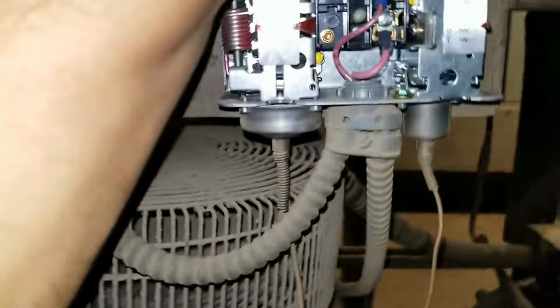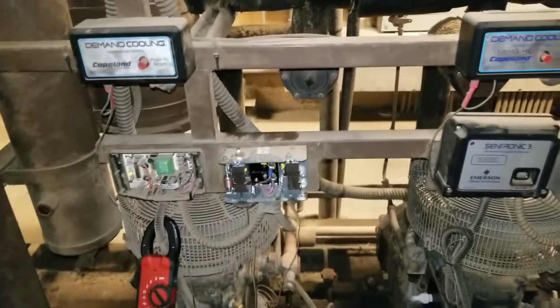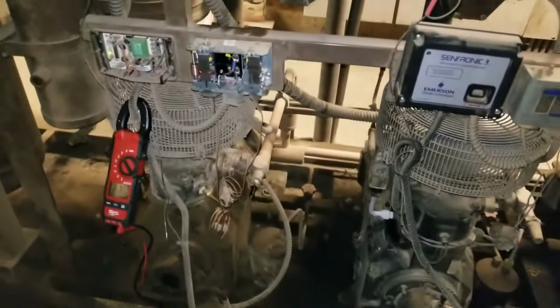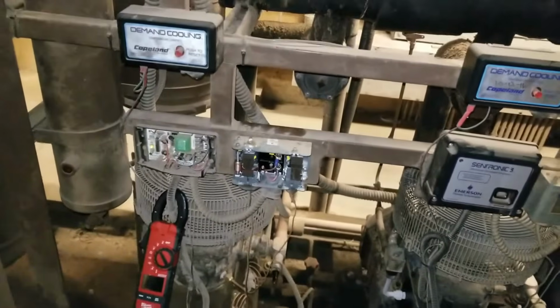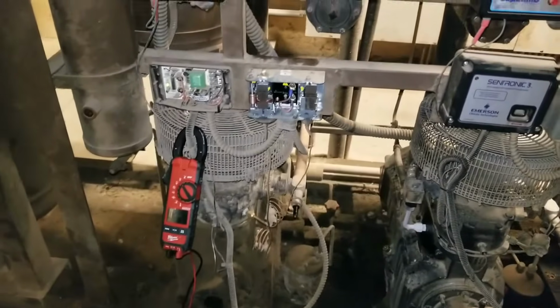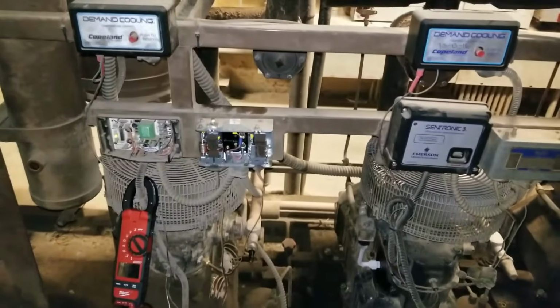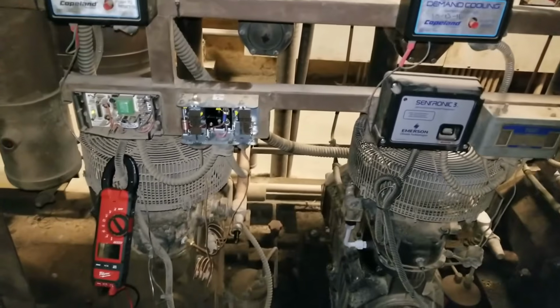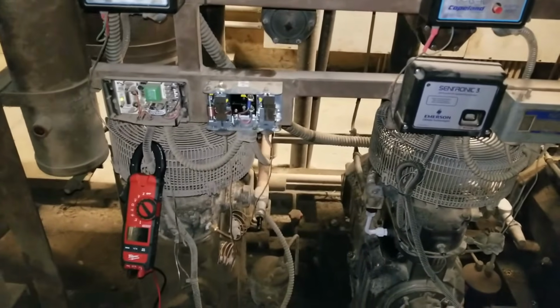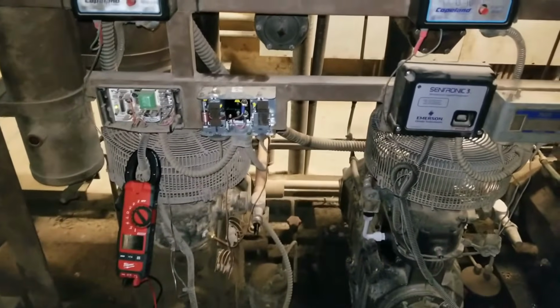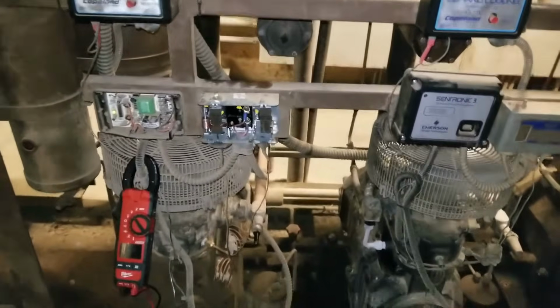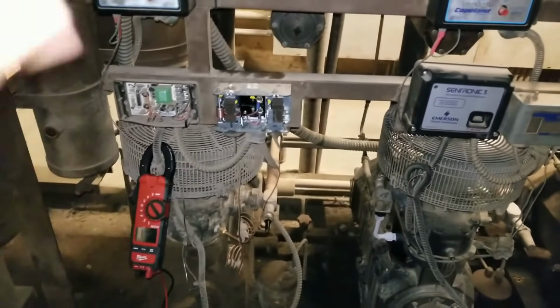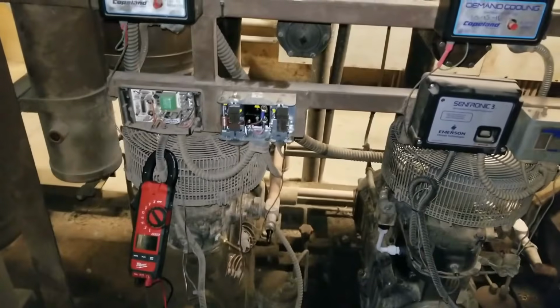The reason why I raised it up a little bit is because if you look at your PT chart, it's a little under 300 PSI at 125 to 130 degrees converted for R22 refrigerant. Out here in the desert in California, it gets extremely hot, over 100 degrees. It's at 115, gets to 120 sometimes. So these pressures rise up a lot.